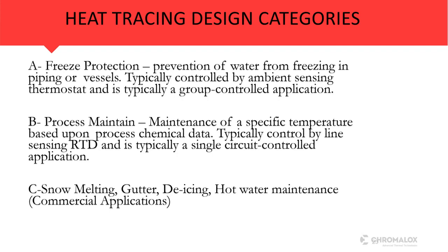Process maintain, on the other hand, is the maintenance of a specific temperature based upon process chemical data, and that's typically a single sense line RTD and a single controlled circuit application. A little different from water in that we need to make sure that we don't overheat. We're looking to heat at a specific flow path, so it's a little different from freeze protection. And then thirdly, we have what we call commercial applications. That's where we're doing snow melting, gutter de-icing, hot water maintenance, those types of applications.